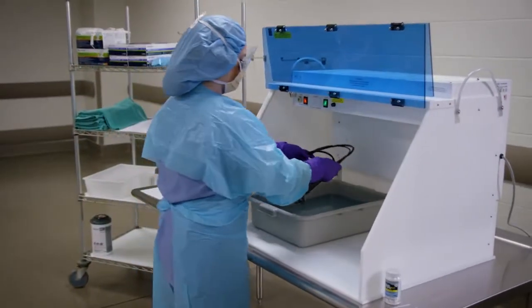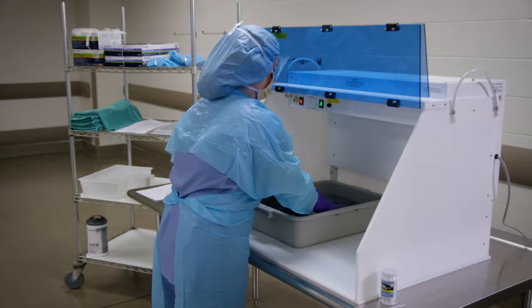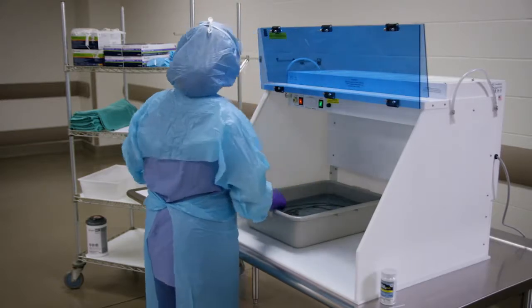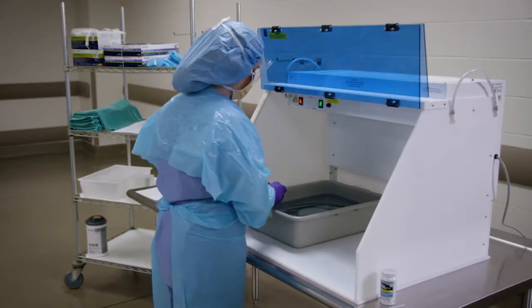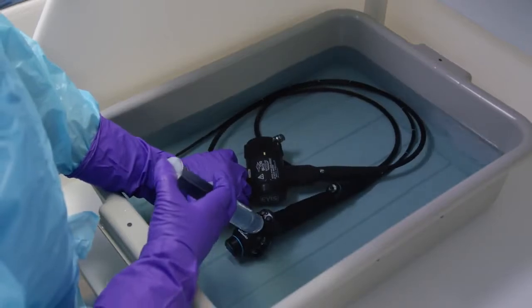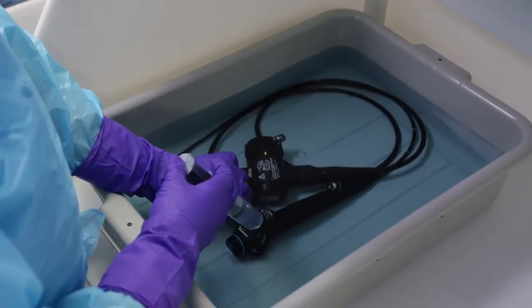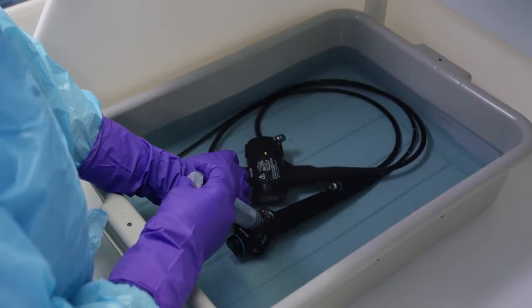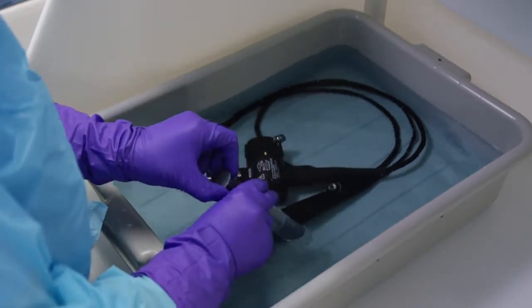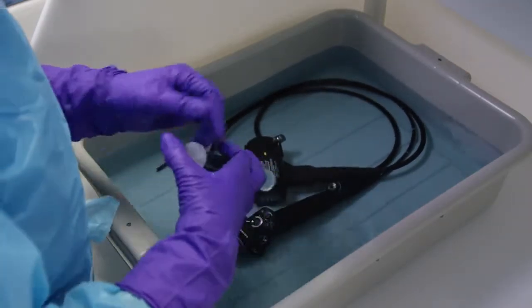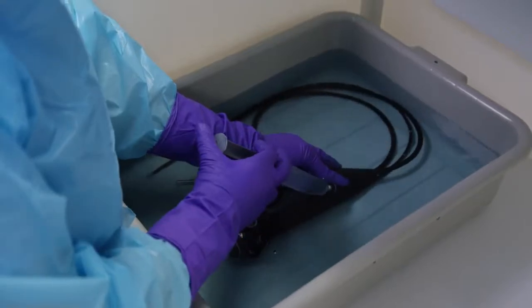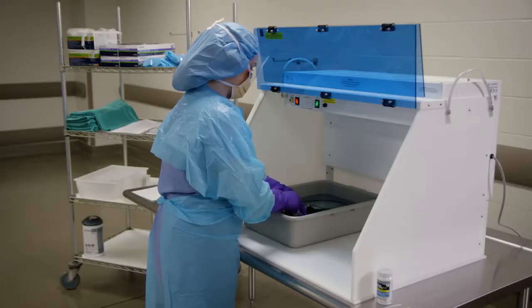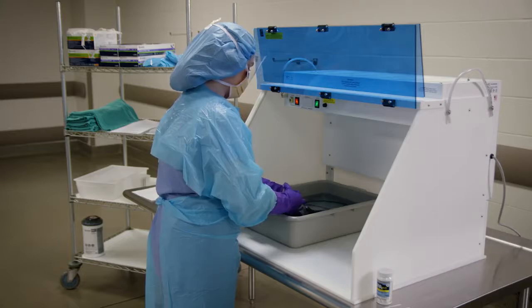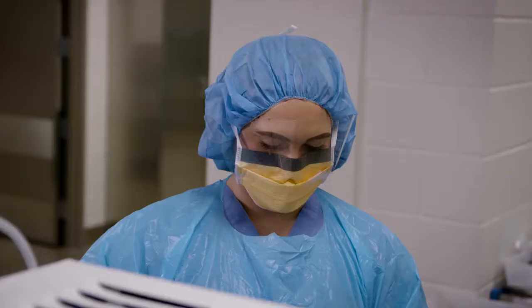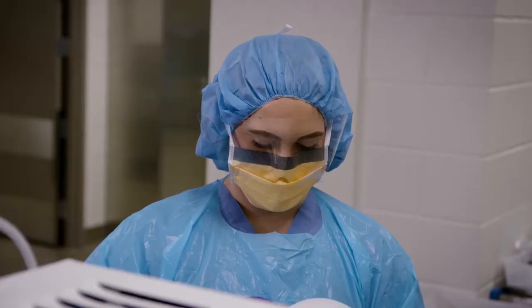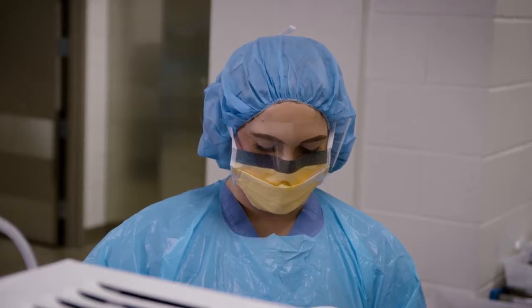But we also have to be thinking about the safety of the personnel here, because to do manual high-level disinfection, somehow you have to perfuse that very strong chemical down the channel. You're going to do that using a syringe, and when you're doing that, you want to make sure that you don't get splashed with that high-level disinfectant or get it in your eye, as very serious injury could happen if that were to occur. In addition, with the manual HLD process, you have the possibility of exposure to the fumes because you're working directly with very strong chemicals.